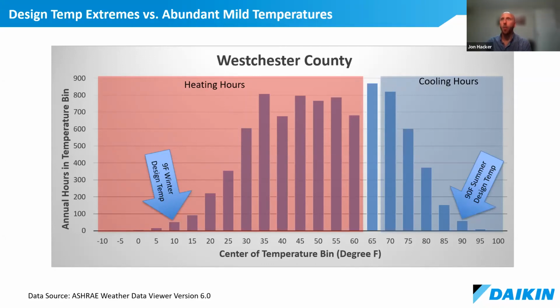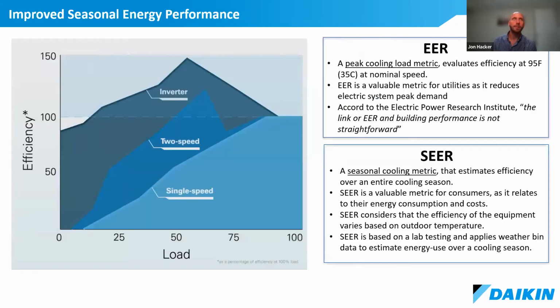And that's when an inverter system is going to provide the most benefit, both in terms of comfort, but also efficiency, because it's not operating at 100% load, but it's operating at part load. And the same is true for cooling, right? So we design and size the equipment for 90 degrees Fahrenheit, but a large majority of the cooling season, it's not that warm and loads aren't that high, right? So again, a lot of those cooling season hours are at 80 degrees and below, where the equipment can modulate, provide comfort, and operate more efficiently.